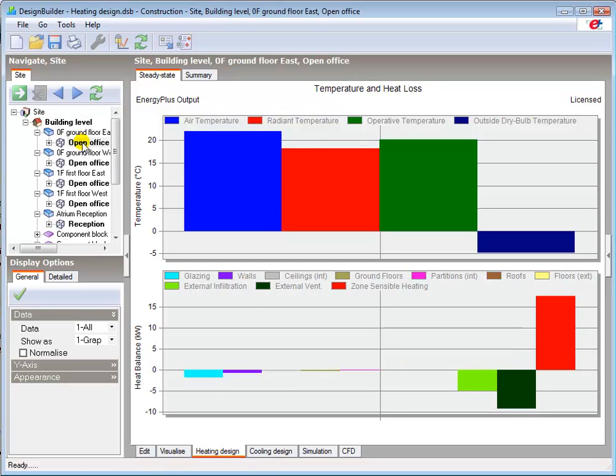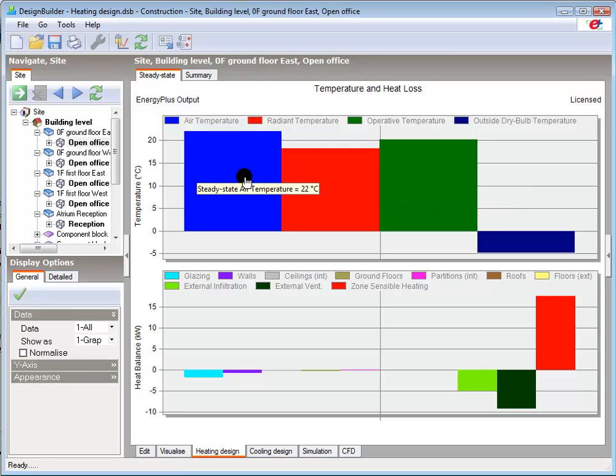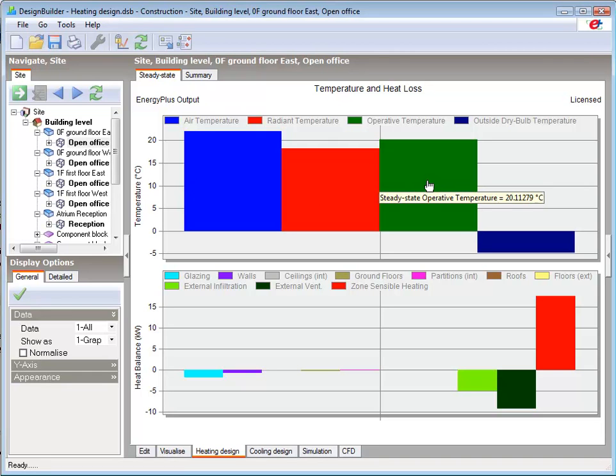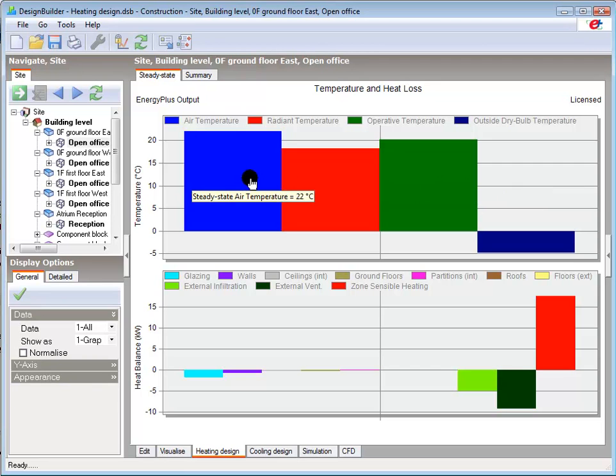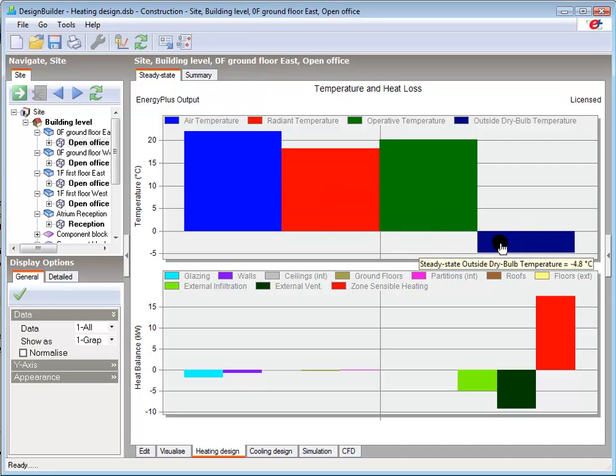Going to the ground floor east office we can see that the average operative or comfort temperature is around 2 degrees C lower than the zone set point because air temperature was set as the control parameter. The operative or comfort temperature as it is sometimes called is a combination of the air and radiant temperatures and is a measure of the average perceived temperature in each zone. The external design winter temperature of minus 4.8 degrees C is shown in the blue to the right of the internal temperatures.